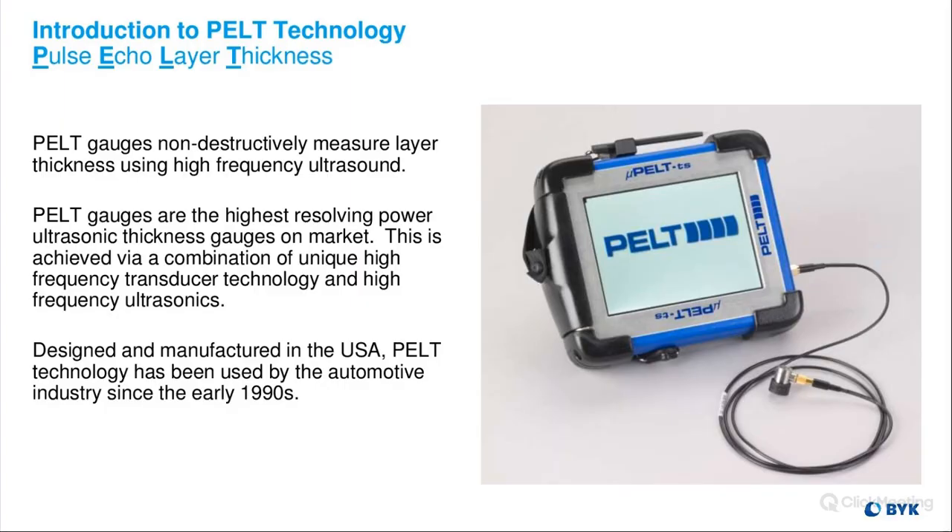What does PELT actually mean? It is an acronym — it stands for Pulse Echo Layer Thickness. PELT gauges are non-destructive and they measure thickness using very high-frequency ultrasound. PELT gauges have the highest resolving power of any ultrasonic thickness gauges on the market, achieved via a combination of unique high-frequency transducer technology and high-frequency ultrasonics. Our technology was designed and manufactured in the USA, and PELT technology has been used in the automotive industry since the early 1990s.